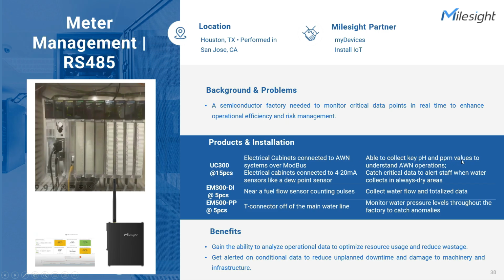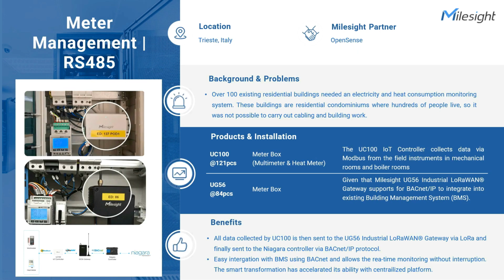And some UC controllers are connected to dew-point sensors that use 4 to 20 milliampere analog signals, sending alerts if water pools in areas that should stay bone dry. Next, for fuel and water tracking, they place 5 pieces of EM300DI near fuel flow sensors to count pulses and calculate fuel usage. Added EM500 pipe pressure sensors on the main water line, using T-connectors to watch for pressure drops or spikes, catching leaks or blockages fast.